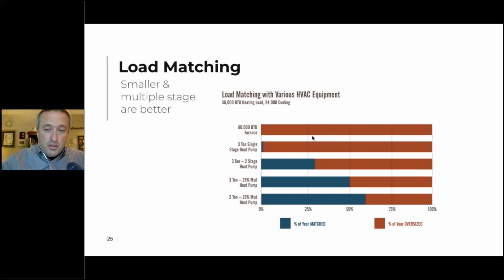So red here is that it's oversized, it can't match. And the blue is where it can match. So that 80,000 BTU furnace, it is wrong all year. It is never the right piece of equipment. When something is sized well, it shouldn't shut off when it's a very hot or a very cold day. Now, if we do, say we right size that and we put in a 3-ton single stage heat pump, then in theory, we can match it about 1% of the year when it's cold.